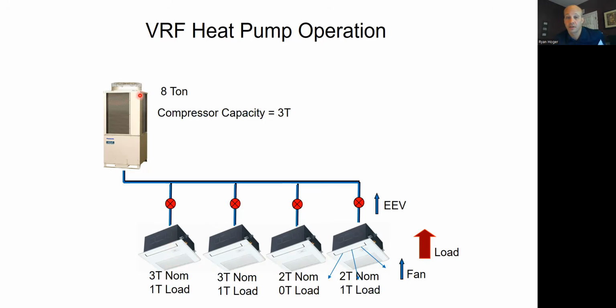How the hell is that going to work? We're banking on the fact that all 4 of these zones are not calling for the maximum amount of heating or cooling at the exact same moment in time. So it is very common to put more indoor units than outdoor. Each manufacturer's model has different rules. They'll allow you to add 20%, 30, 40%, right, above whatever this is on here that you can call connected capacity.